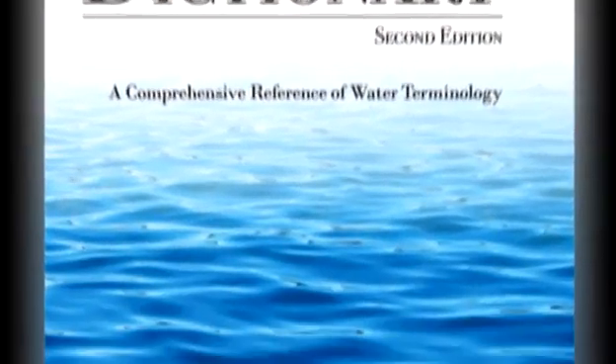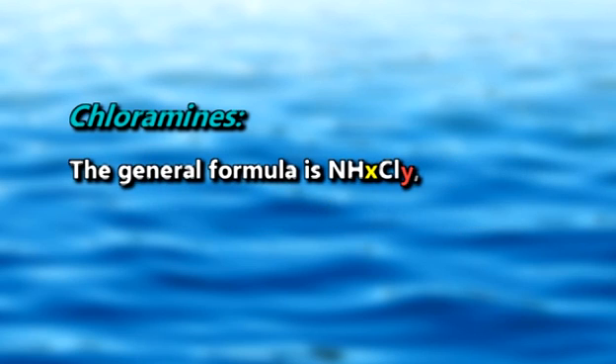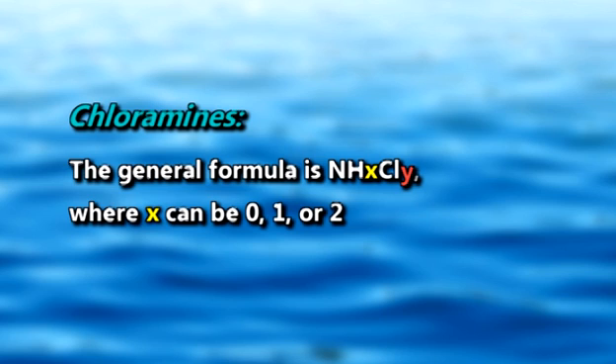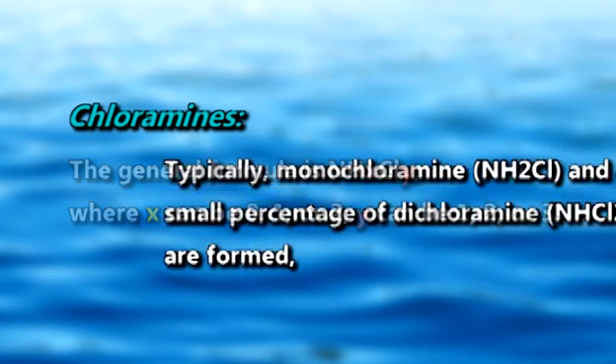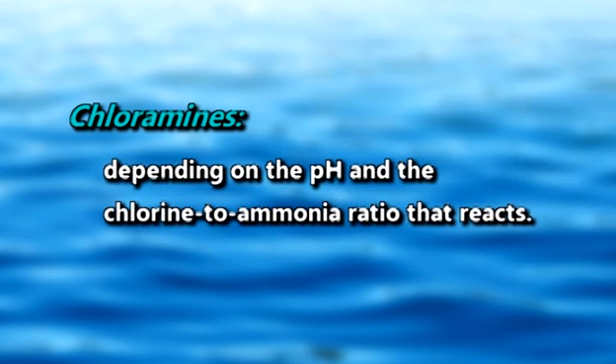The AWWA Water Dictionary defines chloramines as disinfectants produced from the mixing of chlorine and ammonia. The general formula is NH_X CL_Y, where X can be 0, 1, or 2, and Y can be 1, 2, or 3. Typically, monochloramine and a small percentage of dichloramine are formed depending on the pH and the chlorine to ammonia ratio. The intended result is to produce monochloramine.